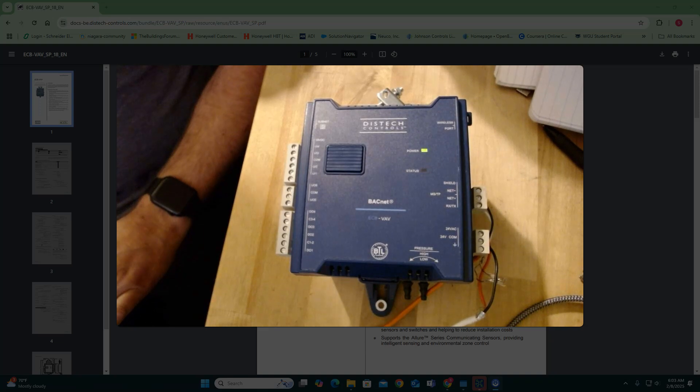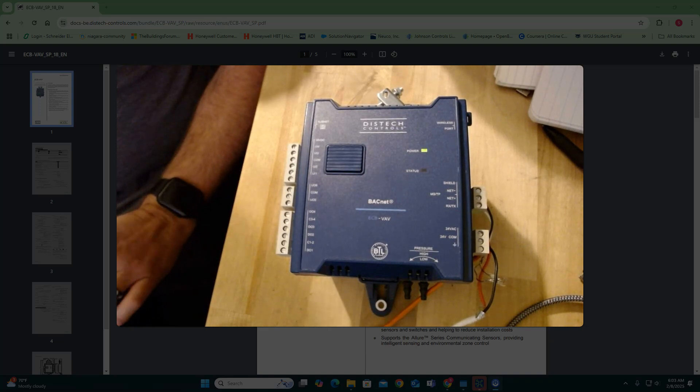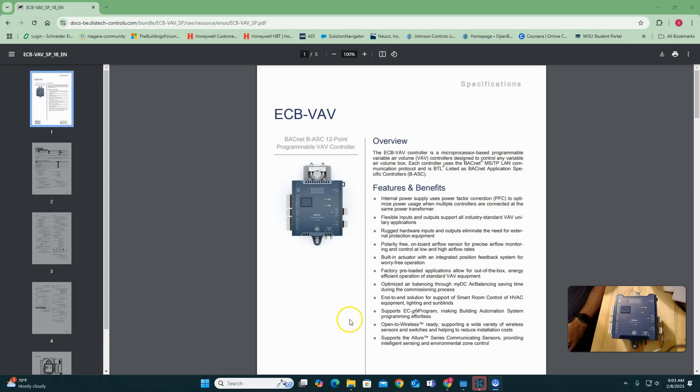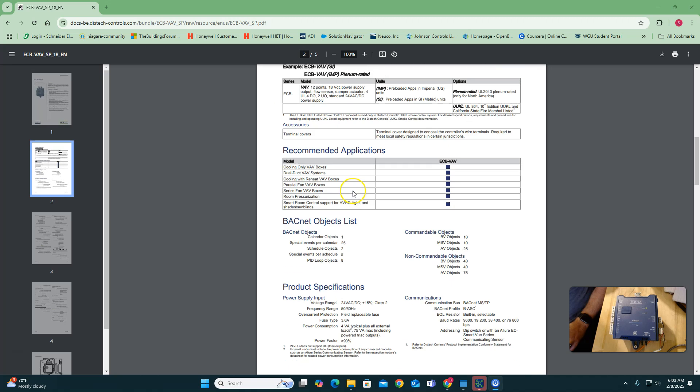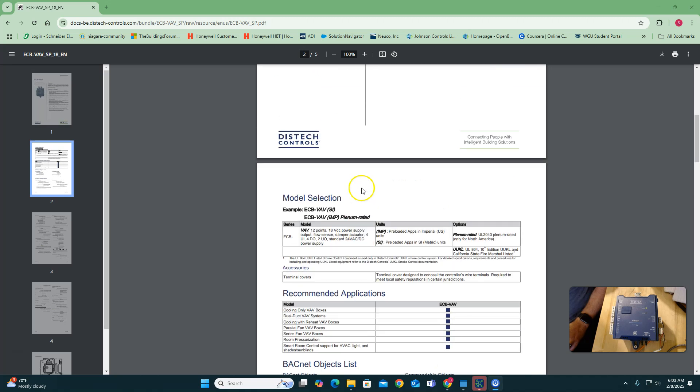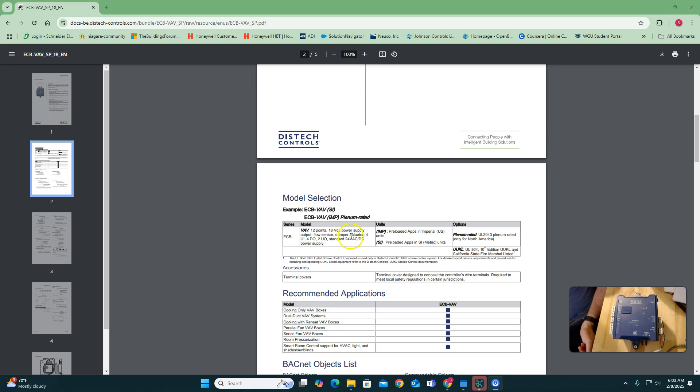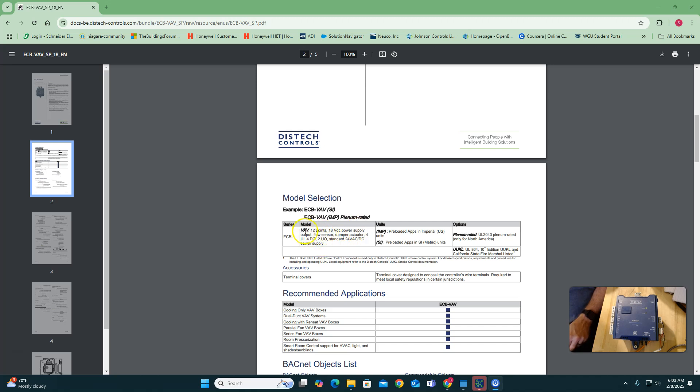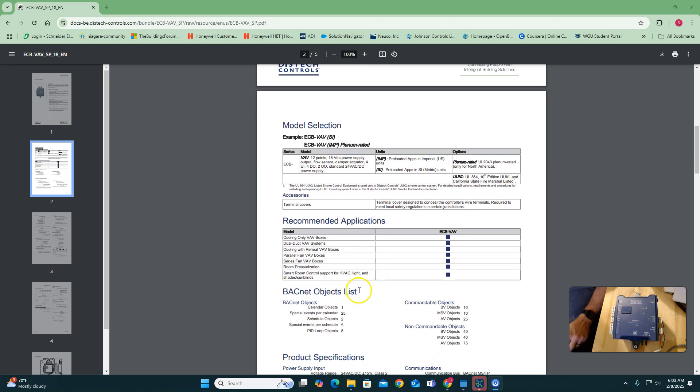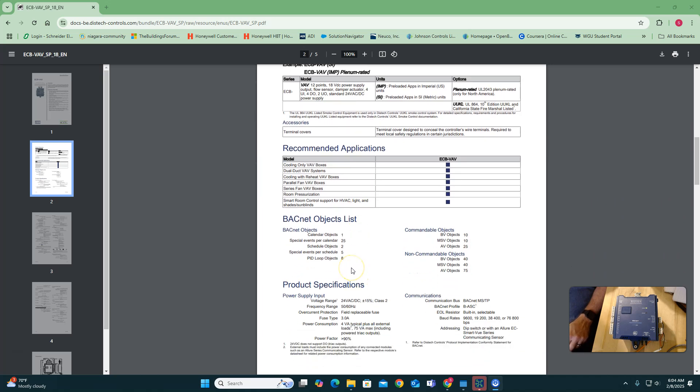But then when I went to documentation, just to be honest with you, I found this and it says 12 points. So I was like, oh, they must make a bigger version of this. But no, the 12 points, they actually count the damper actuator and the flow sensor as a point, I believe. Again, comment if I'm wrong here. But they even specify four universal inputs, four DOs, two universal outputs. Four plus four is eight, plus two is ten. So they have to be counting something else for that to happen.